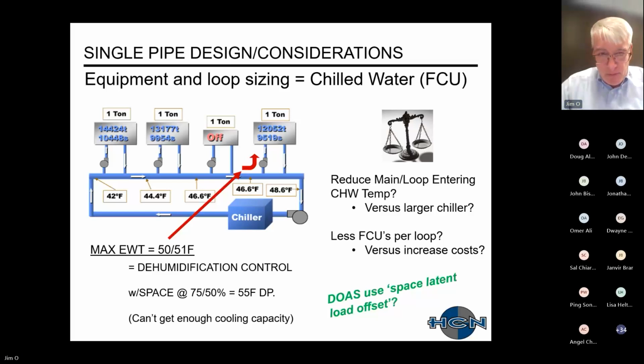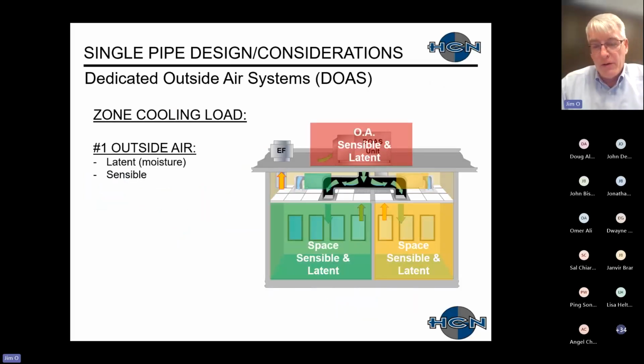All right. And then the other thing to consider, or maybe a little trick to help out with your dehumidification control, is that these terminal units traditionally don't have outside air into them, and what's commonly done is to add a dedicated outside air system. And there is a way that you can use something called latent space load offset, where you can reduce your leaving air temperature to help with your latent cooling load in the space. All right, just a quick sidebar.